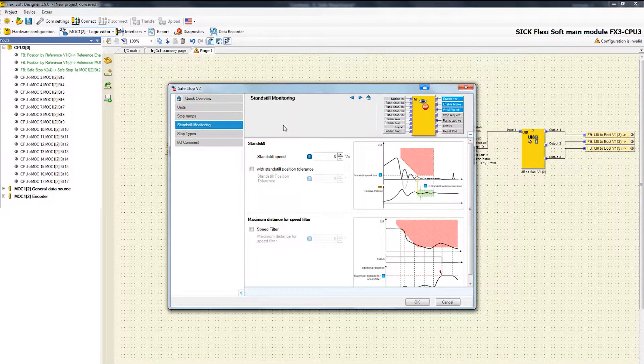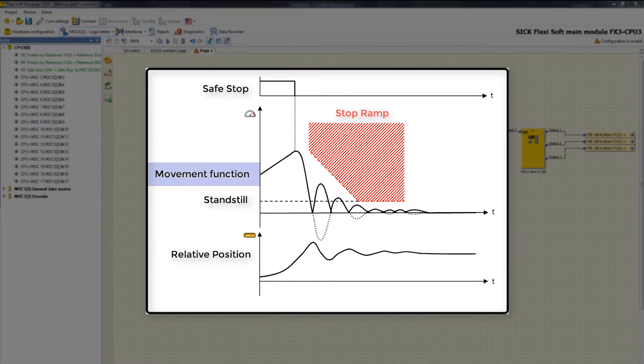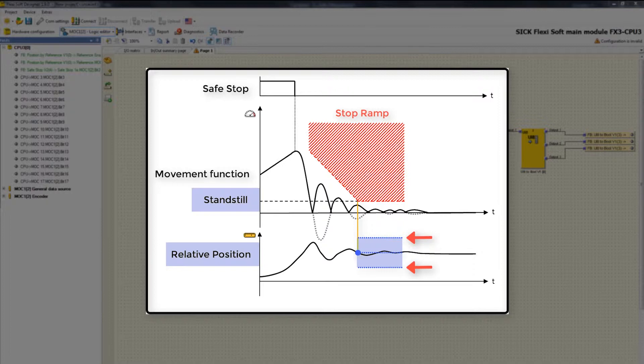Let's go to the next tab, Standstill Monitoring. After defining the standstill speed, we have the possibility to activate the standstill position tolerance window, where we can define which relative position change still counts as a standstill. In the graphic, when the drive reaches standstill speed, the defined position tolerance window opens and the relative position is monitored permanently. Within this limited window, the drive is allowed to move and it still counts as a standstill. But if the drive exceeds the limits of the window, the torque is cut off immediately.